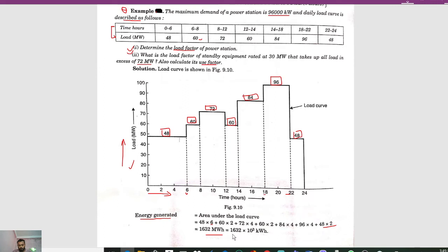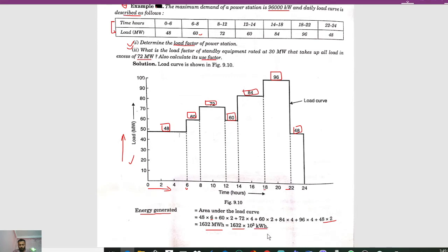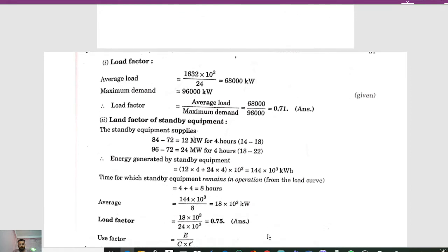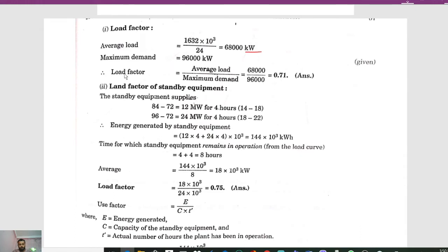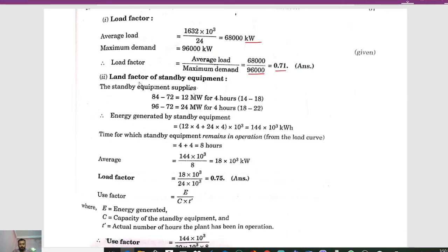For load factor, the average load is calculated by dividing energy generated by 24 hours, giving 68,000 kilowatt. The maximum demand is given as 96,000 kilowatt. The load factor formula is average load divided by maximum demand: 68,000 / 96,000 = 0.71.